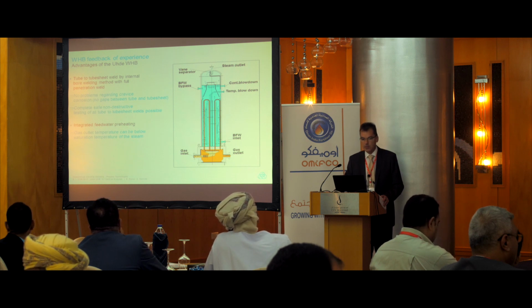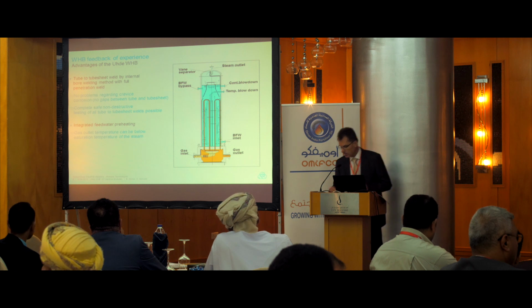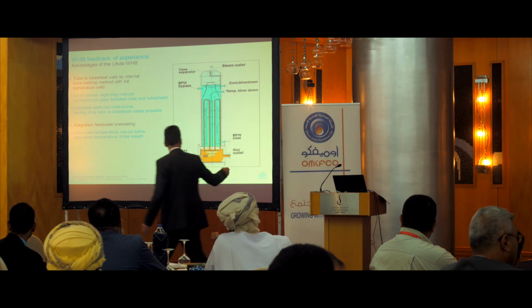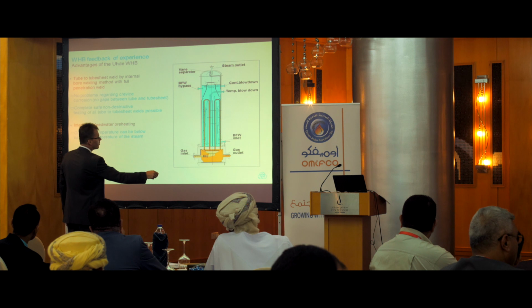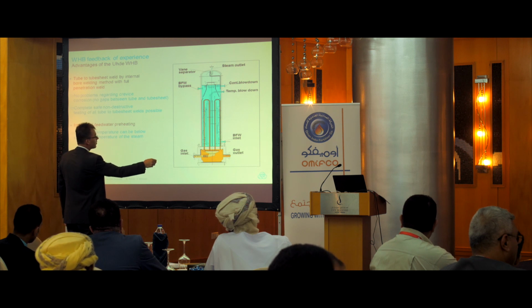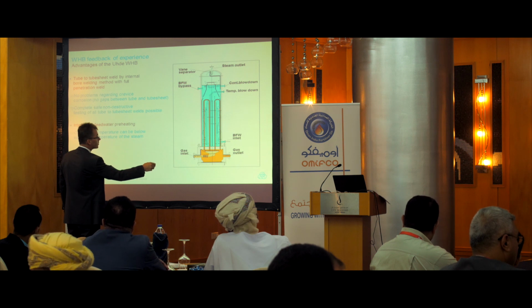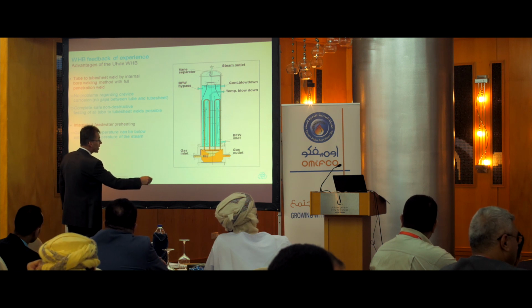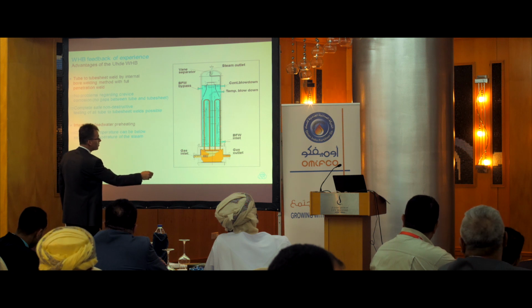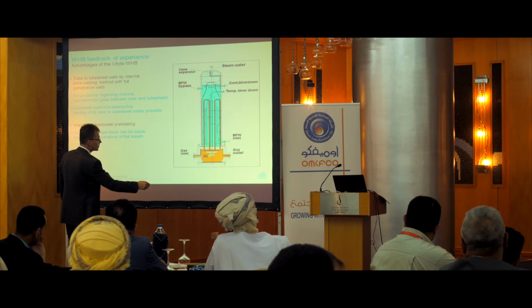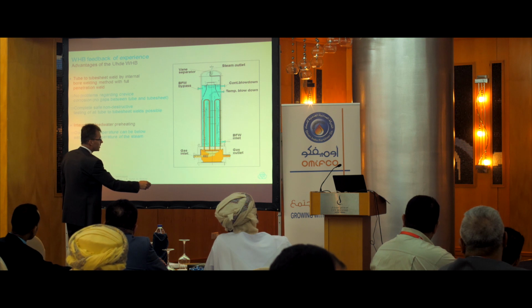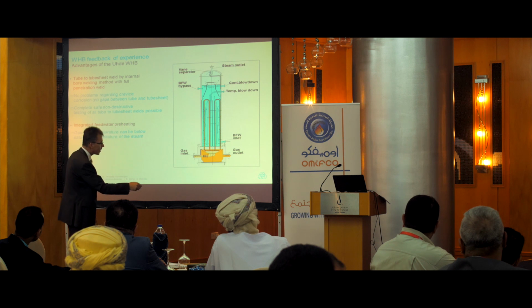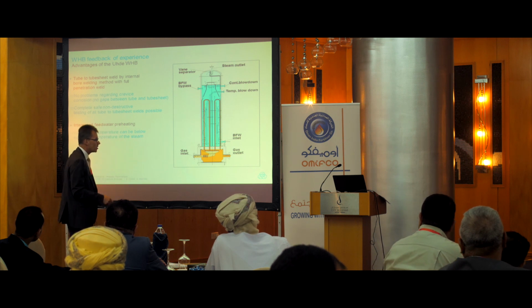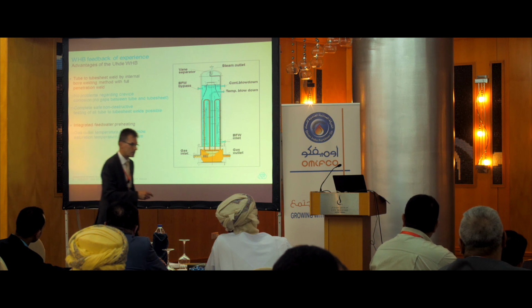And we have a so-called integrated feed water preheating. That means the boiler feed water coming from the right side will be preheated up here. There's an internal shroud, another cylinder in this waste heat boiler. That means the hot gas coming here gets cooled in this area in between, so that we are coming out with a temperature much below the incoming gas temperature, cooling down all this area. Also here I will show you one slide how this looked like, because this is also a nice kind of engineering done here.